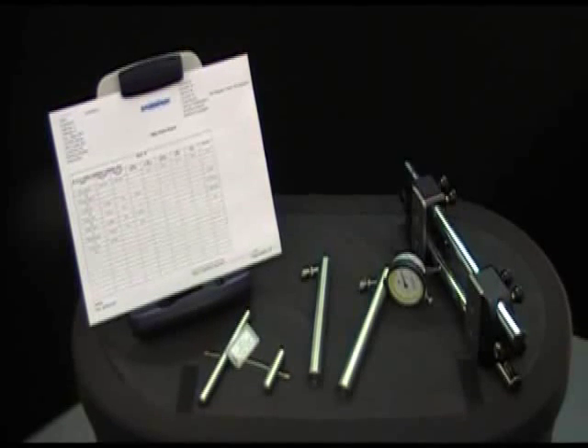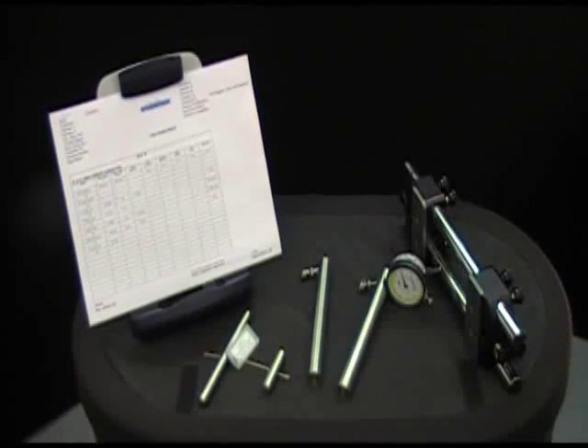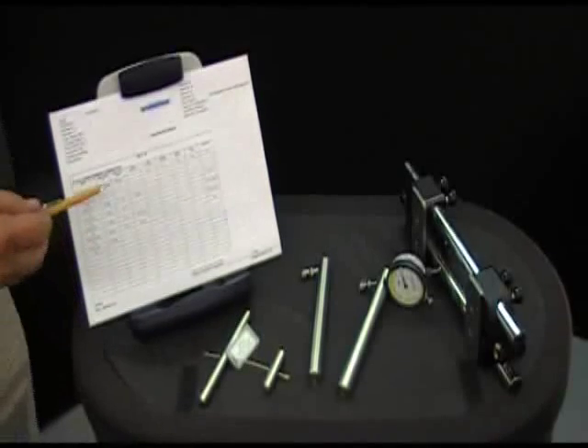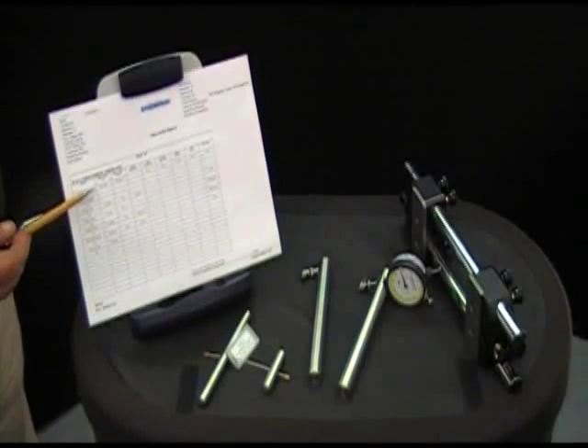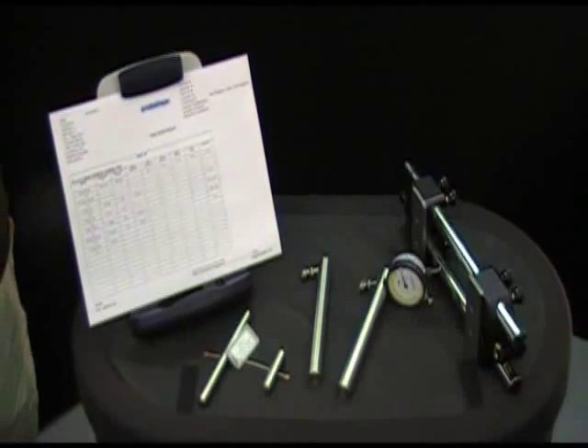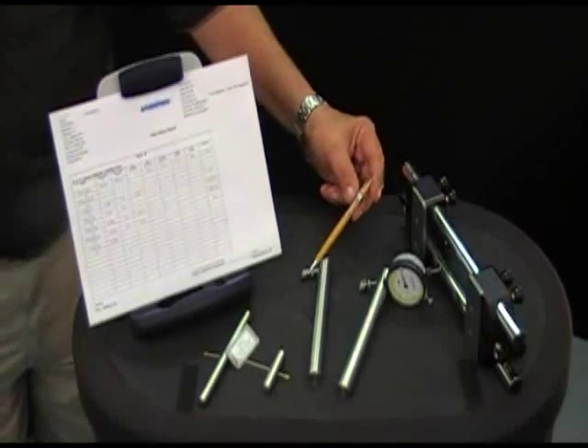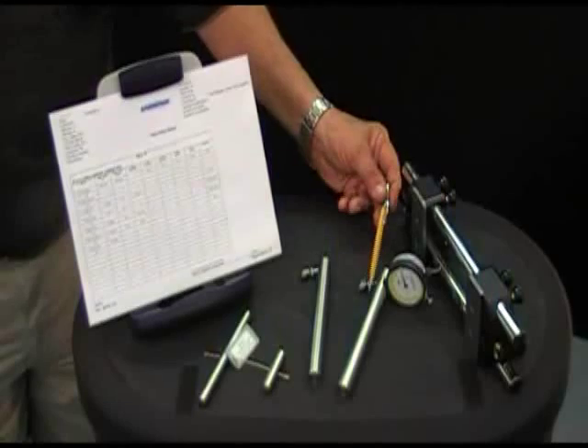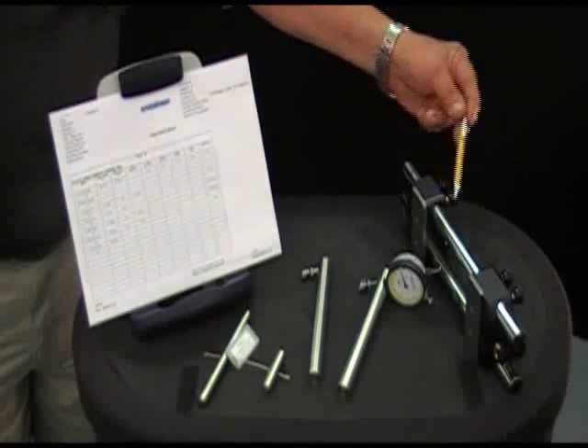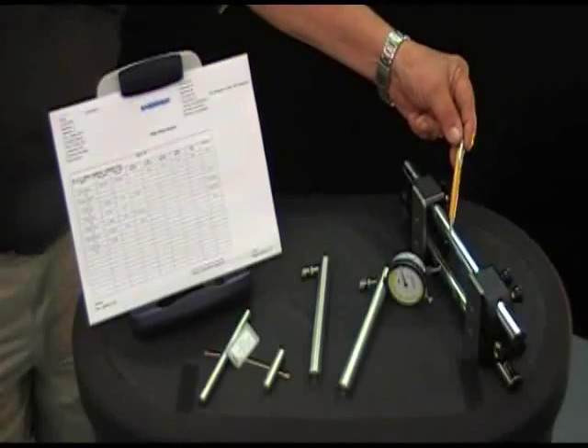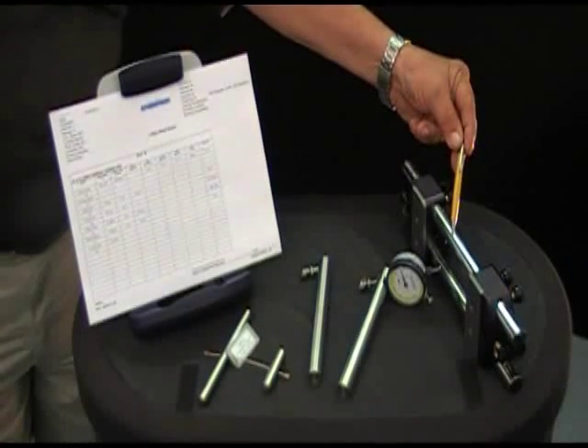Shown here on the display table, starting off with the first column, it tells us our MRP is a MRP 2001, which consists of a lower arm and a shoe, an upper arm and a shoe, and the main body with the rails set up for 7 and 5 eighths and smaller.